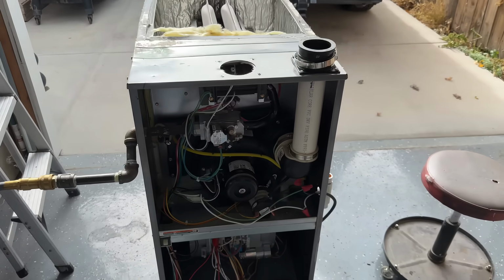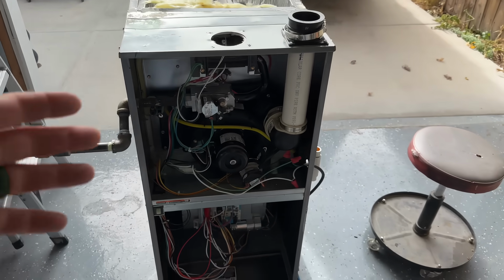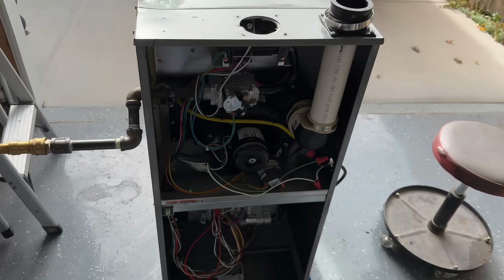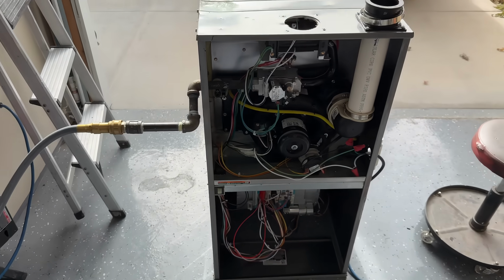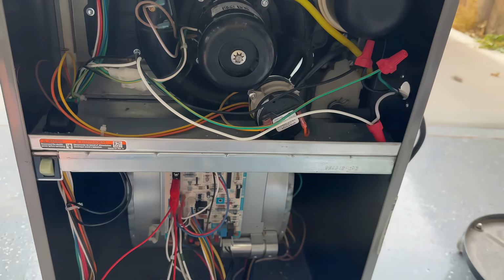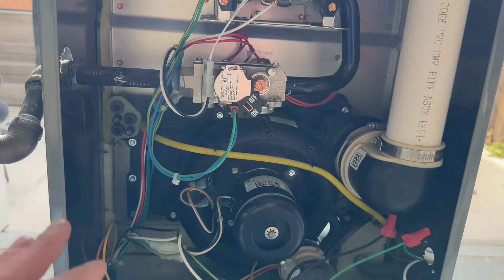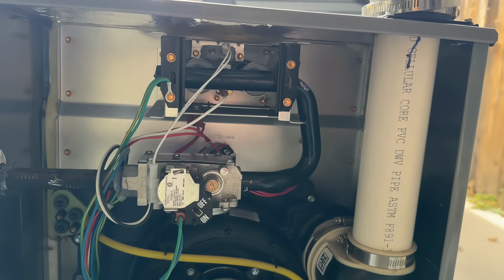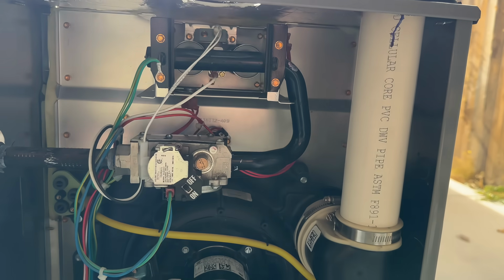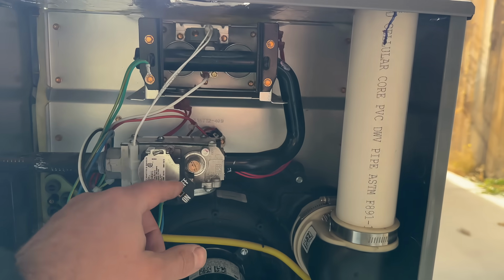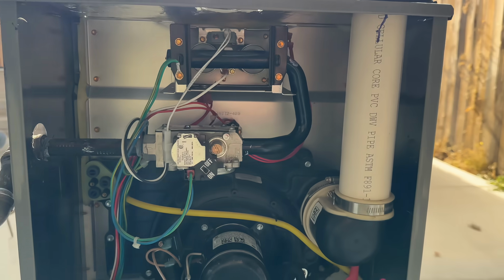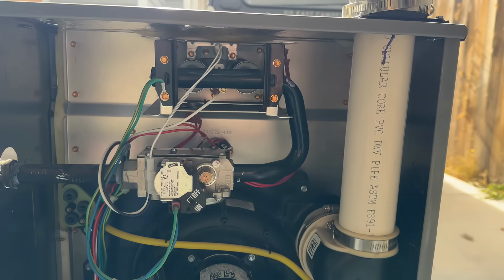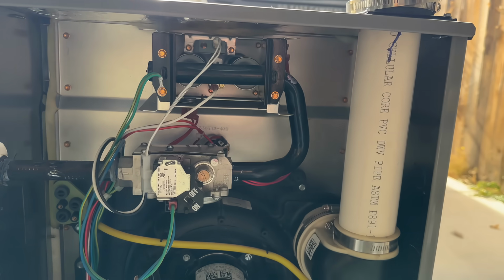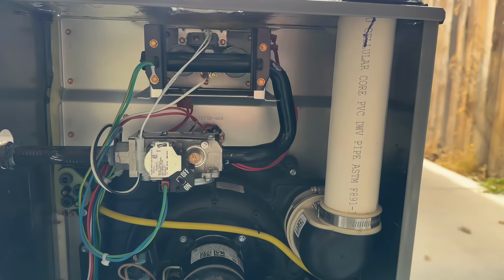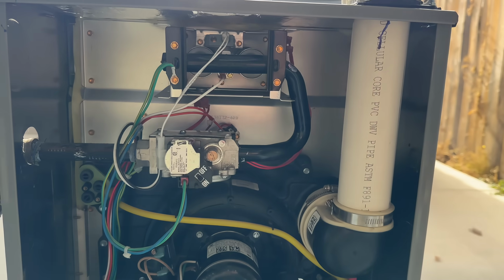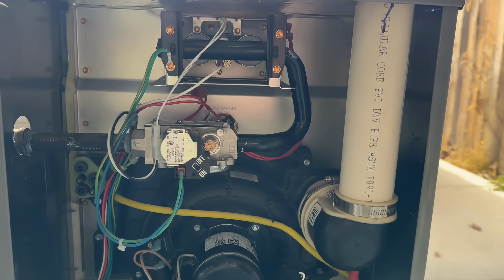Okay, so here's the furnace that we're going to be demonstrating on. This is obviously out of the home and a very temporary setup. We just have a temporary gas line and our electrical connected here. But we're going to show you how this gas furnace should turn on, what you can expect when your gas furnace comes on. Then we're going to duplicate a cracked heat exchanger and show you how you can test to see if it does have a crack. And if you're still uncertain, we're going to show you some other measures you can take to test if you have a cracked heat exchanger.